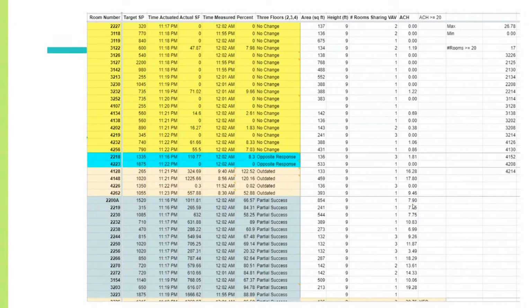If you go room by room, you have to go up into the false ceiling and look for it and see if the damper is stuck. On the other hand, if you write a program and set a target set point, for example, this particular room, 1520 cubic feet per minute, but when we actually set it to maximum, we only get 66% of the maximum, that means the valve is getting stuck. So we identified rooms where such valves are stuck.